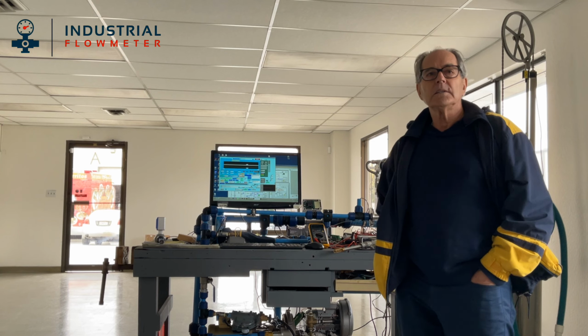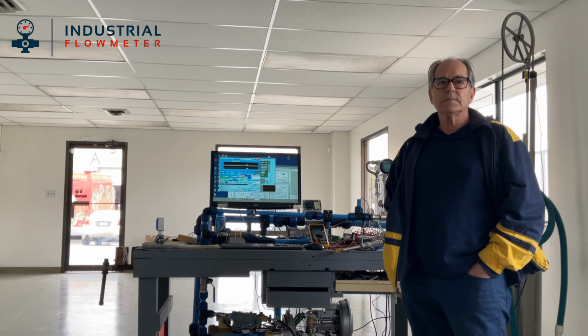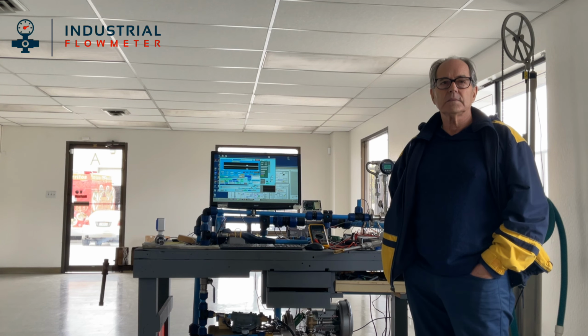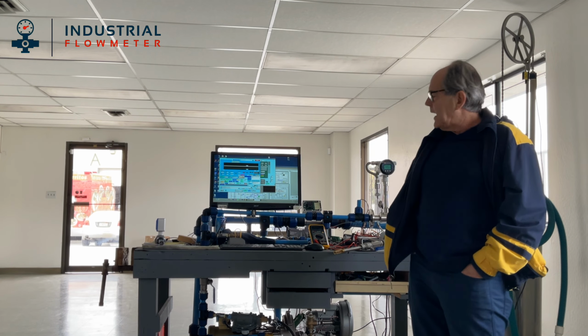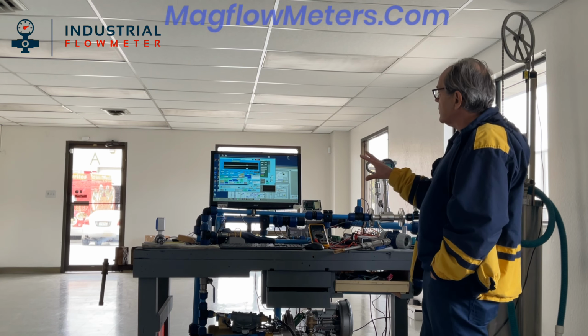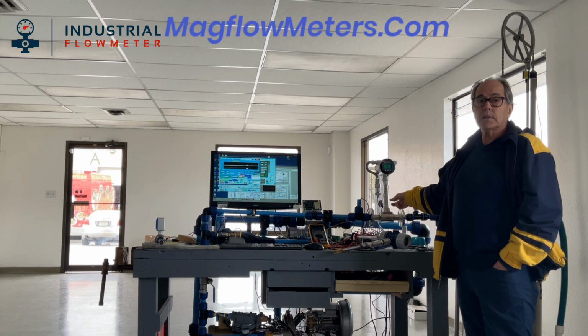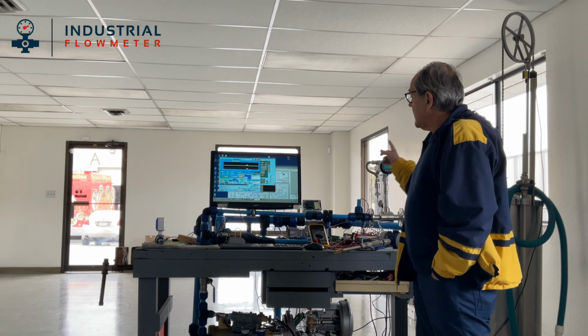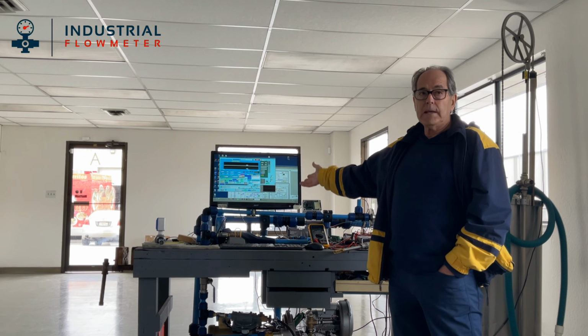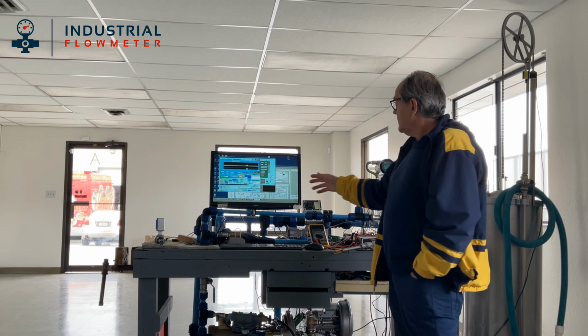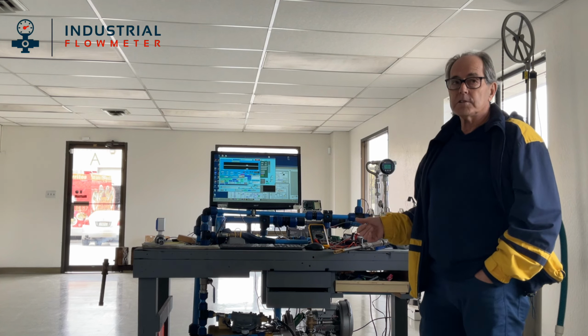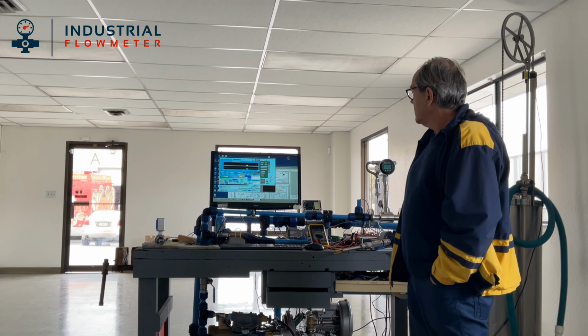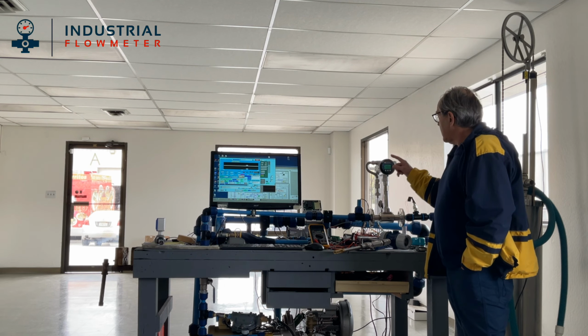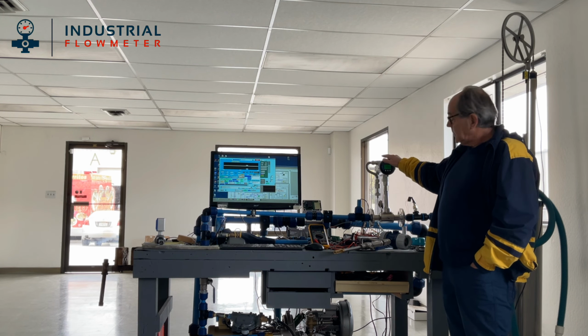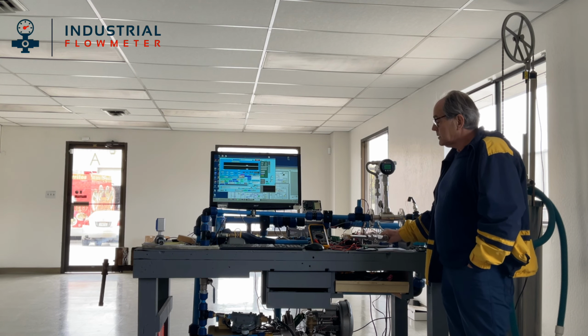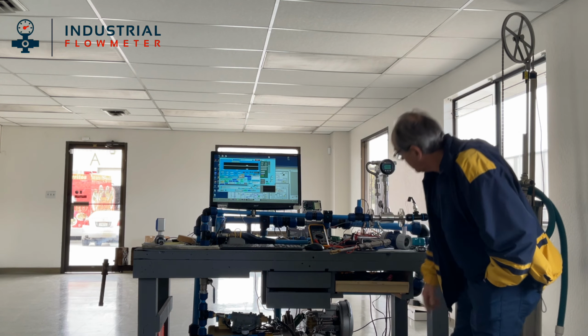Yeah. This is basically a really, really good calibration system that we can use to find and subtract out any of the errors in the flow meter. And I would say this is a method of characterizing a flow measuring instrument. So it characterizes and it speaks in its native tongue, which we've made standard cubic feet per minute, that can be converted to any unit at any reference temperature and any reference pressure, and then take that characterization, program it inside of any device. This device or this device or the other one, wherever that one went.